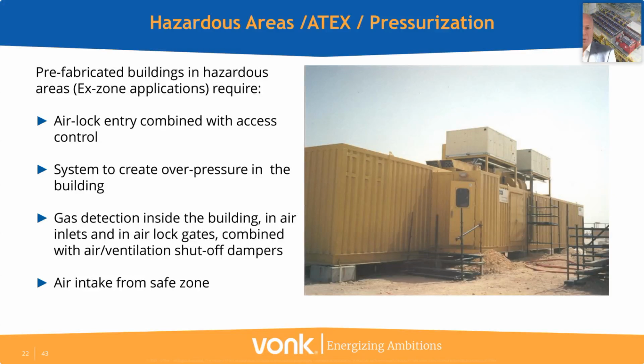Often in the case of chemical or oil and gas plants, you can have hazardous areas. You can have different kinds of combustible or toxic gases escaping from other installations. And you want to protect your prefabricated building against it, of course. So then you will have a separate and special airlock entry combined with access control. You see that as the little steps in the yellow building, where you see the door. There's actually a kind of separate part at the side of the building. You want to create overpressure in your building, so the gas from the outside cannot enter. And there is special gas detection inside, of course, also using air ventilation and shut-off dampers. And you want to take your fresh air in from a safe zone, which could sometimes be quite a distance away from your building.